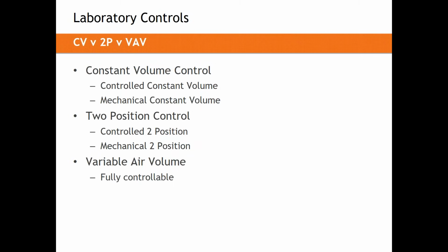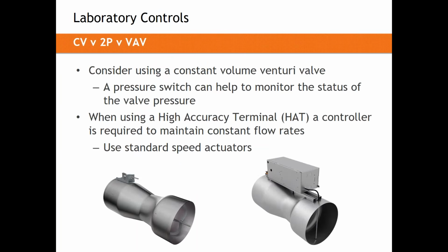The last one we'll talk about here is the full VAV control. For both devices, whether it's a high accuracy terminal or a Venturi valve, the equipment is extremely similar. You need a controller, you need an actuator, and in some cases you need the transducer to measure that flow, and you can achieve anywhere from minimum to maximum flow on that box. So how can we apply these devices?